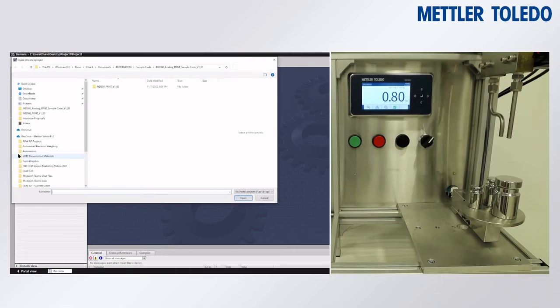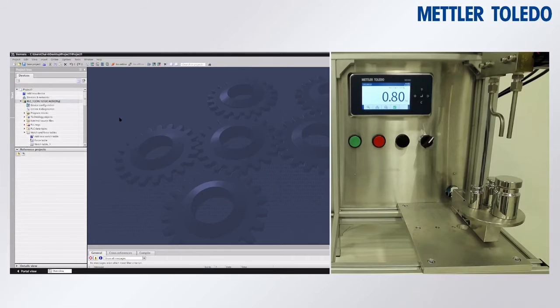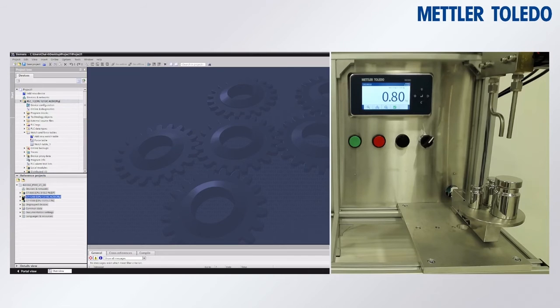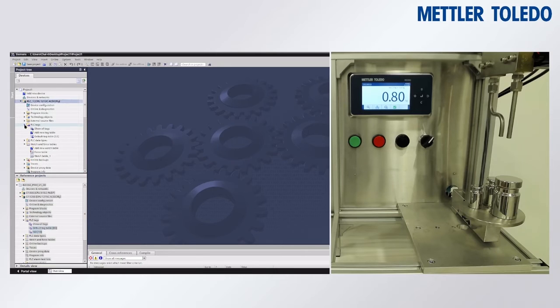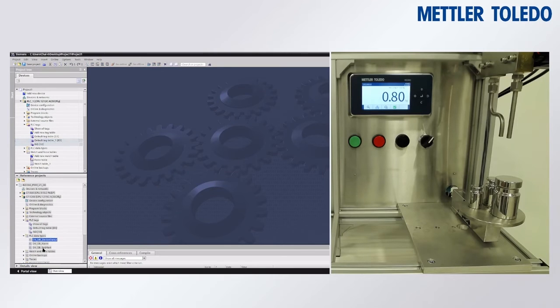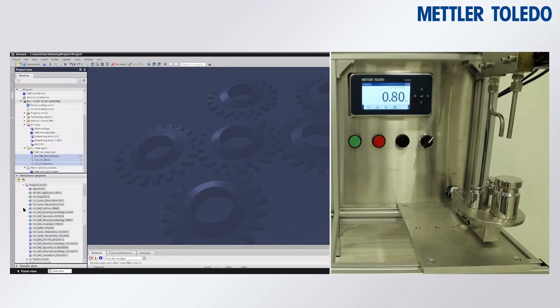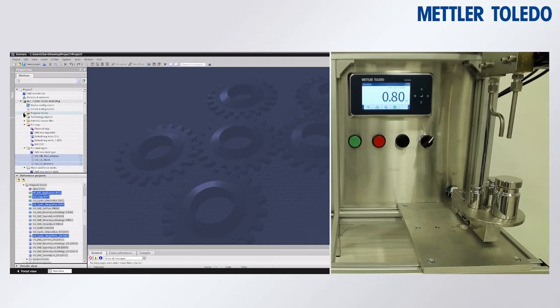We'll go offline and incorporate elements from our sample code. We'll add the sample code as a reference project so we can copy and paste the elements we need to use the weight data processing block. We'll copy and paste all of the PLC tags from the sample code project into our new project, then go to PLC data types and copy and paste all the data types from the sample code. In the program blocks, we can pick and choose — since we're only using the weight processing block, we don't need to copy every element.